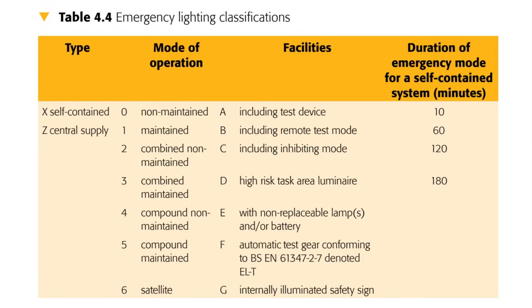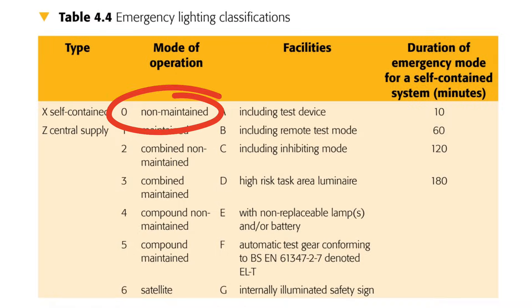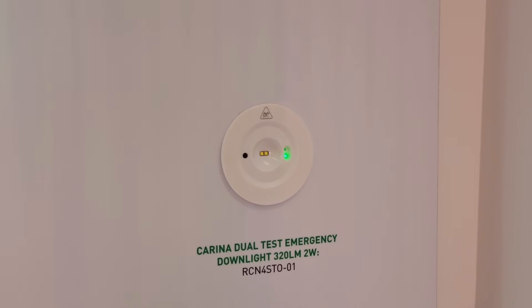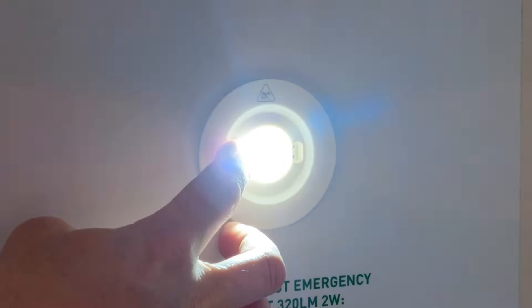In BS5266-1, we find Annex F, which describes seven different modes of operation that emergency lights can operate under. These are reproduced in Table 4.4 of the Electrician's Guide to Emergency Lighting, and each one is given a number from zero to six. Mode zero is non-maintained. This means the fitting is never illuminated as long as the supply is healthy. When the supply fails due to a power cut, a fault that operates the circuit protective device, or some other reason, the battery inside the light fitting will connect to the light source and keep it illuminated. If the power is then restored, the battery will start to recharge ready for the next power failure.